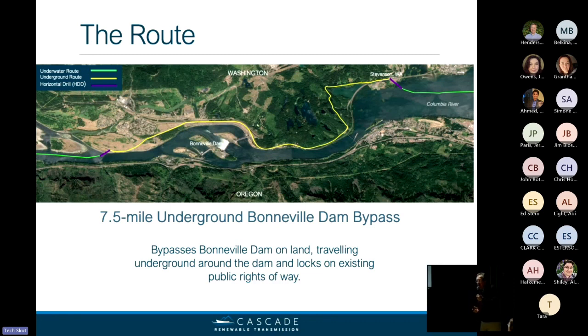Now, horizontal directional drill, that's where we actually drill underneath. Once we've got the borehole to size, then we'll pull the conduit back, and then we can use that conduit to land the submarine cable onto land, where we create the transition joint that allows us to connect the underground design to the submarine design.